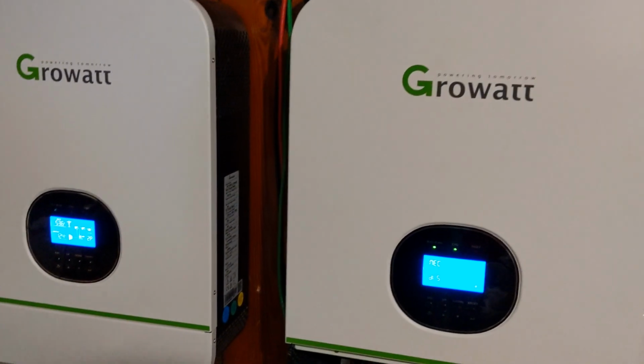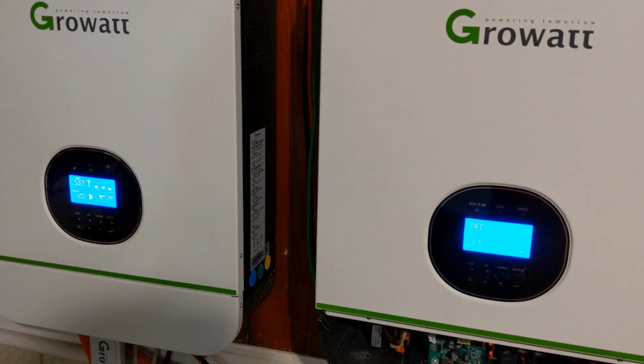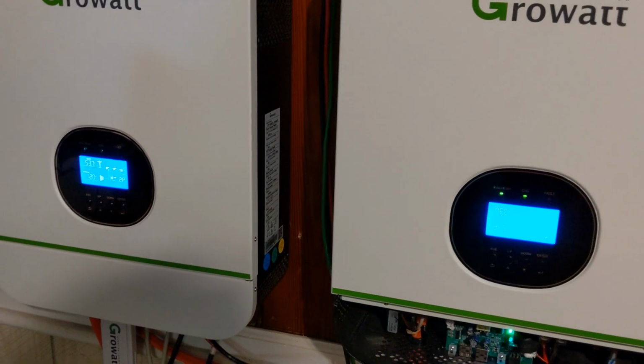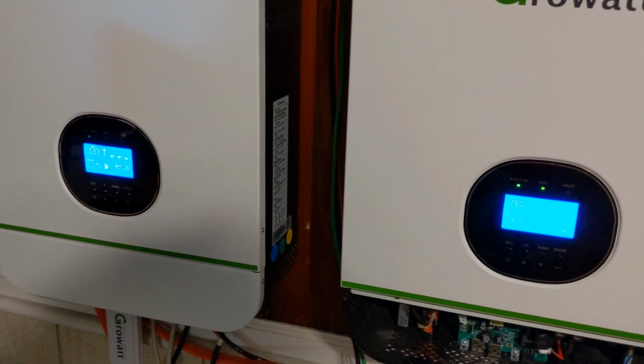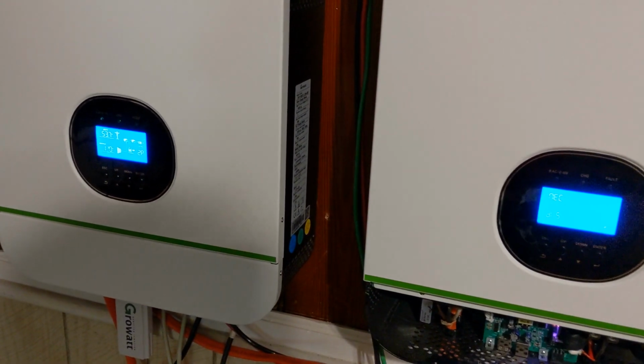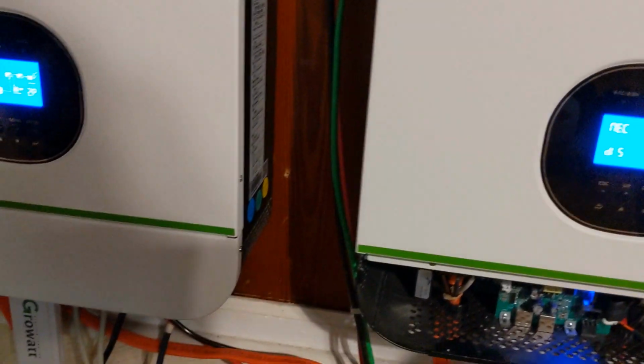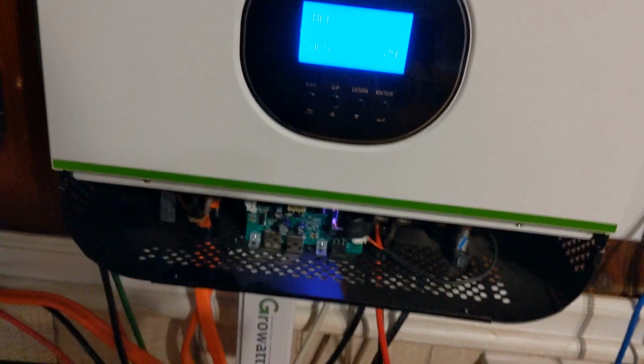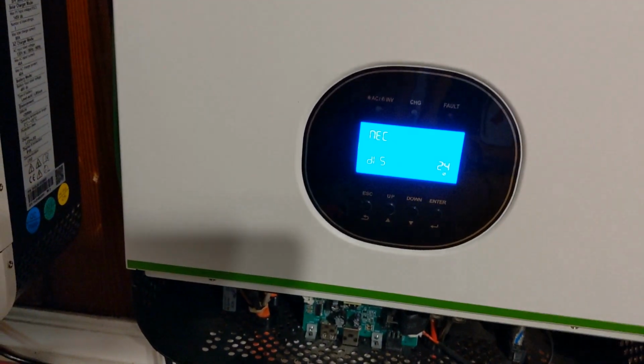So if you put in 4 of these, you'd have 3,000 watts per inverter on each phase. So that would give you 6,000 watts on phase 1, 6,000 watts on phase 2. But that's where you set those settings. And again, you can only set that while it's off. That way you can make sure that you set it correctly.